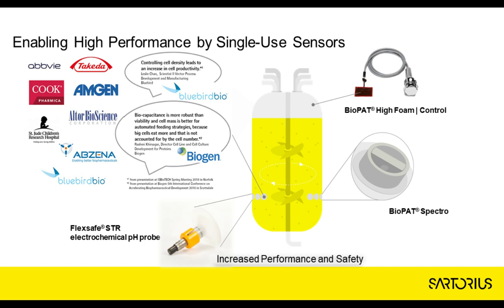Regarding sensors, I would like to focus on single-use technologies, because single-use sensors remove the need to autoclave probes and insert them in the reactor bag chamber. They significantly reduce handling efforts and potential contamination risks, increasing process performance and safety. Moreover, implementing single-use sensors allows us to establish feedback loop controls that ensure reactive process control, avoiding deviations and potential batch failures.